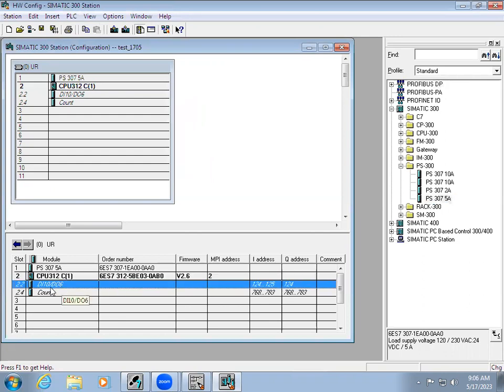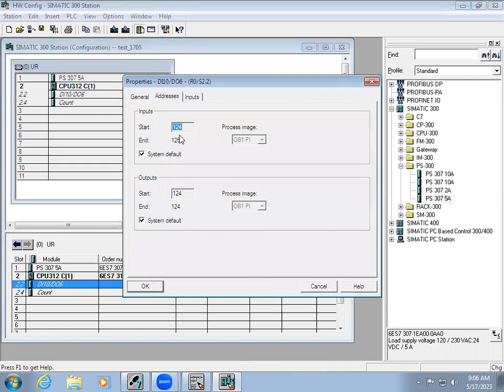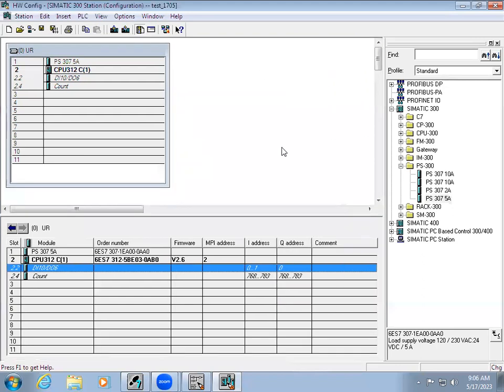You can see the address for digital I/Os — we have 10 digital inputs and 6 digital outputs, and the address being used is 124 and 125. When you double-click you can see the address. The system default is 124; if you remove the system default we can give zero, so in our program we can use address zero onwards. Once you have done the hardware configuration, we have to load it to the controller. Before loading, we have to save and compile.